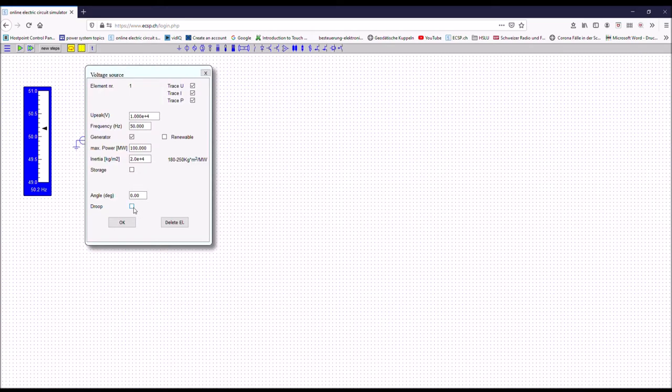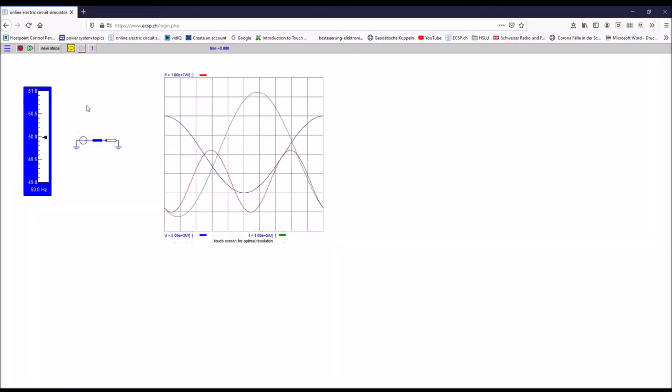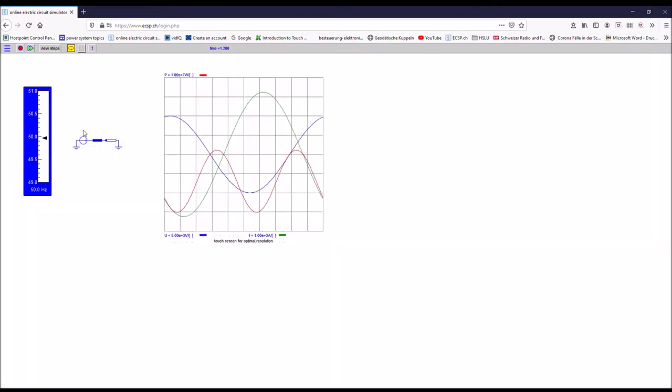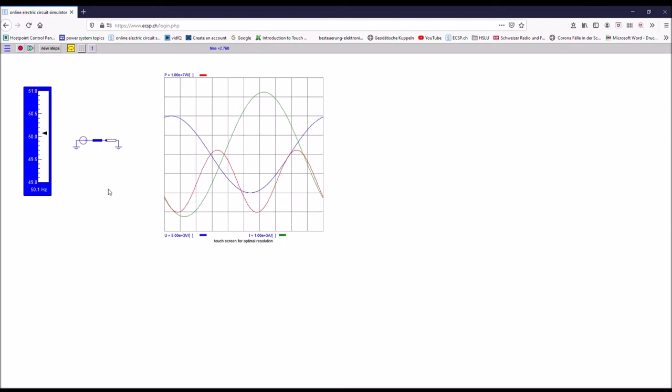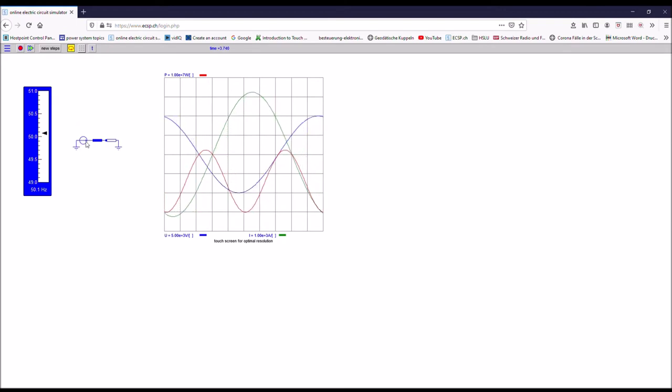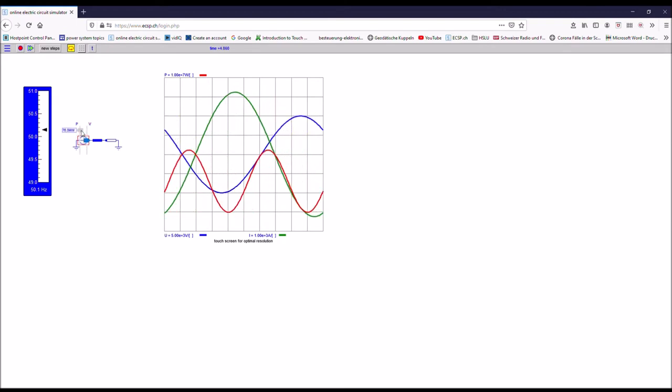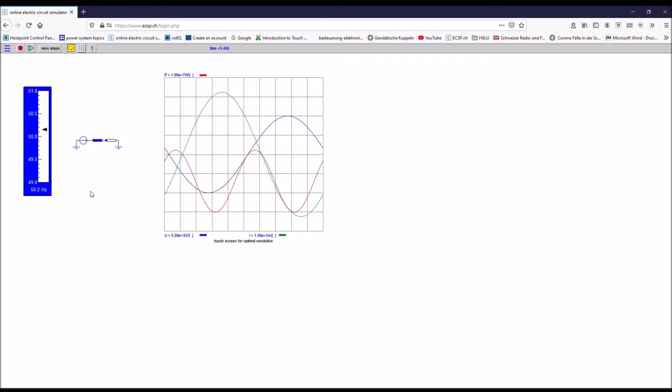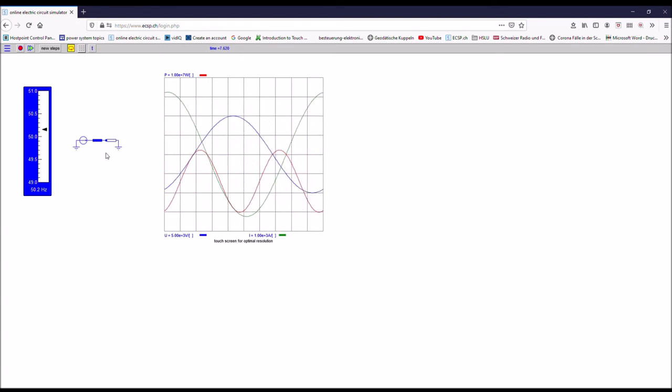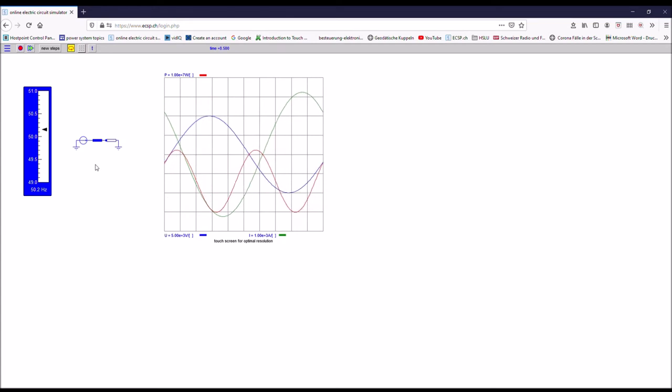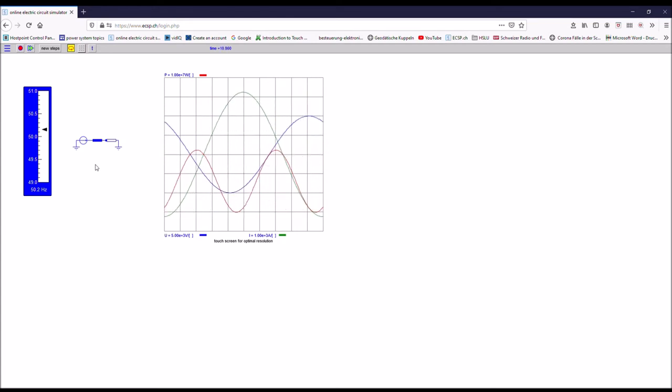So this is the droop checkbox. And as soon as you have the droop checkbox ticked, it will be much easier to control the frequency. The power output will be controlled accordingly. So you can see, even if I push my power output, the real power delivered from the source to the load is limited by the frequency control. And this is exactly what also happens in a real power generation station.